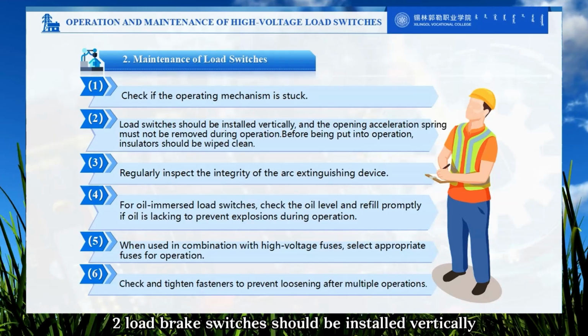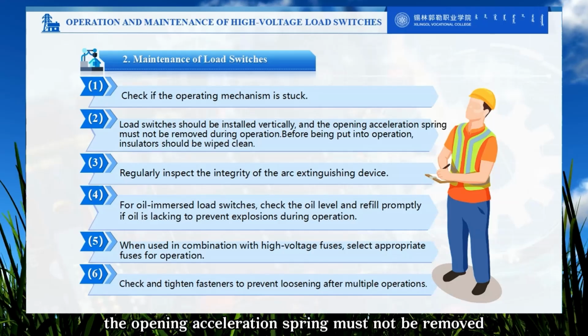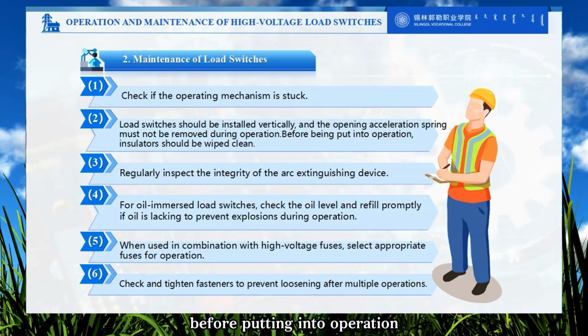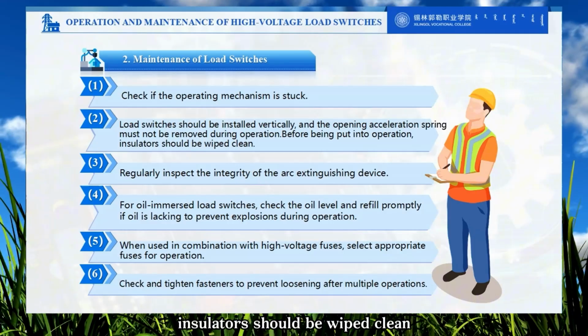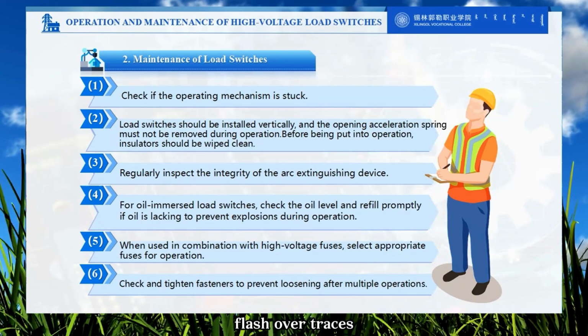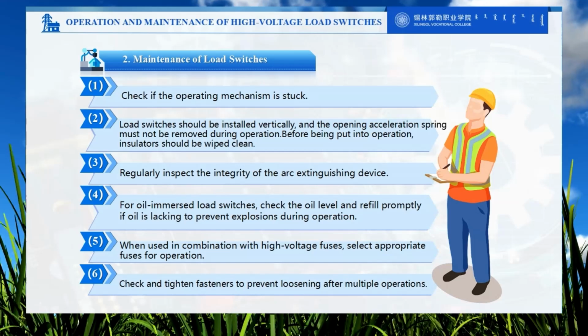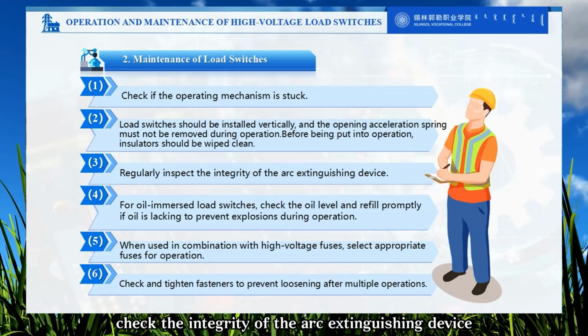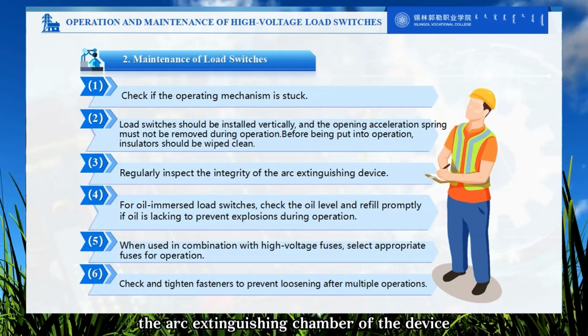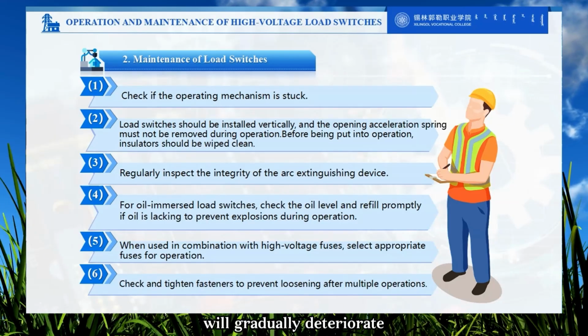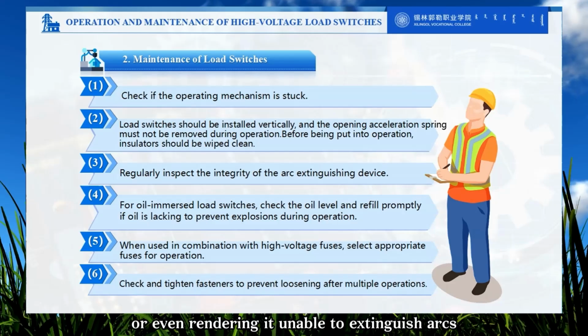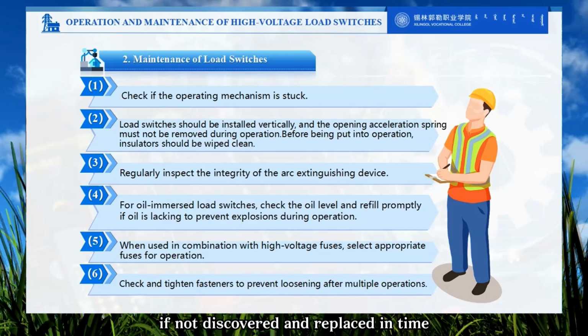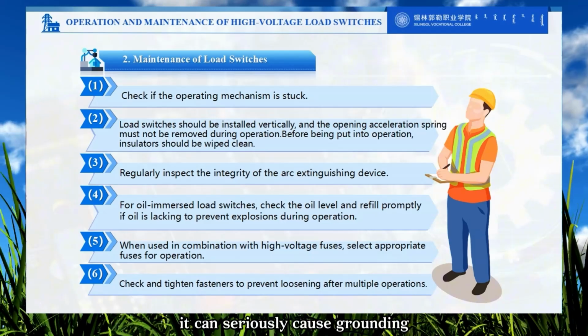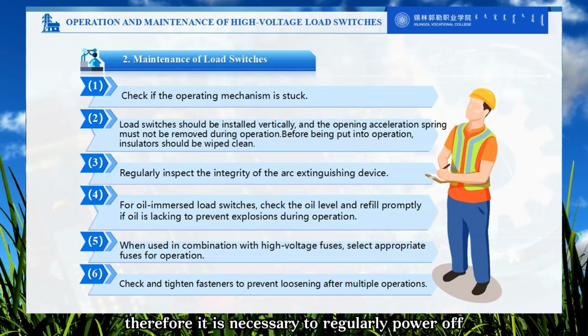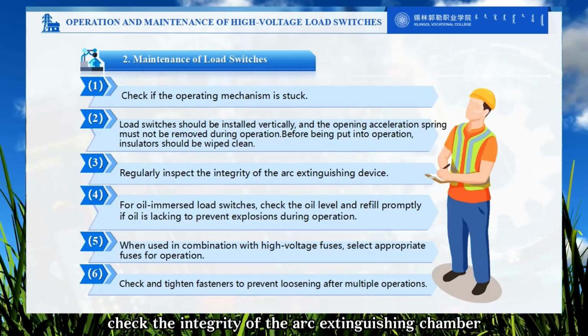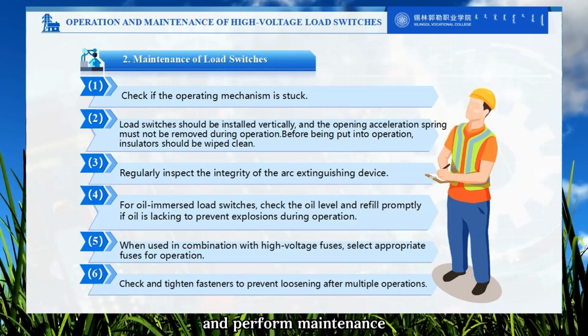2. Load break switches should be installed vertically. During operation, the opening acceleration spring must not be removed. Before putting into operation, insulators should be wiped clean and checked for external damage, defects, flashover traces, and whether the insulation is good. 3. Regularly check the integrity of the arc extinguishing device. After a certain number of operations, the arc extinguishing chamber of the device will gradually deteriorate, reducing its arc extinguishing ability or even rendering it unable to extinguish arcs. If not discovered and replaced in time, it can seriously cause grounding or phase-to-phase short-circuit accidents. Therefore, it is necessary to regularly power off, check the integrity of the arc extinguishing chamber, and perform maintenance.